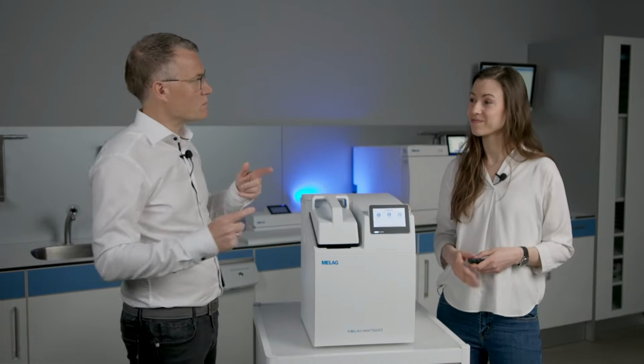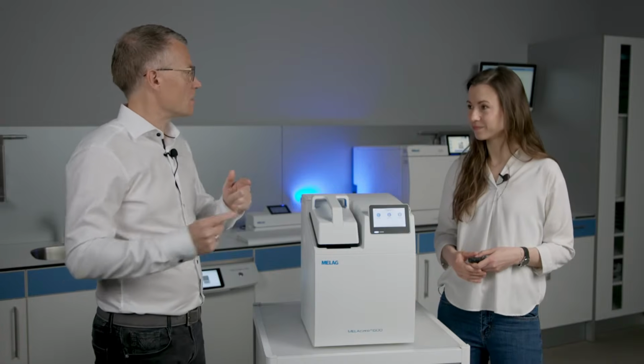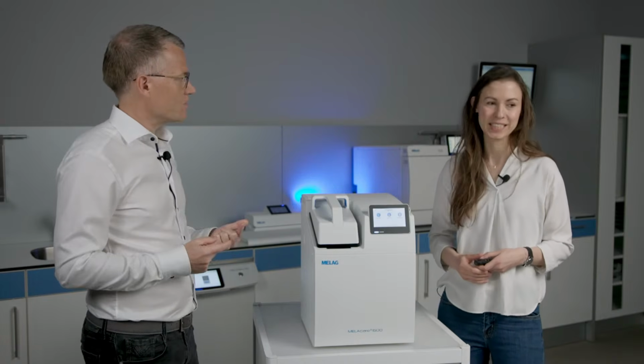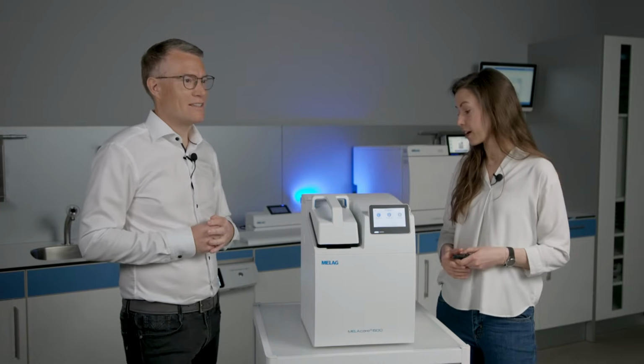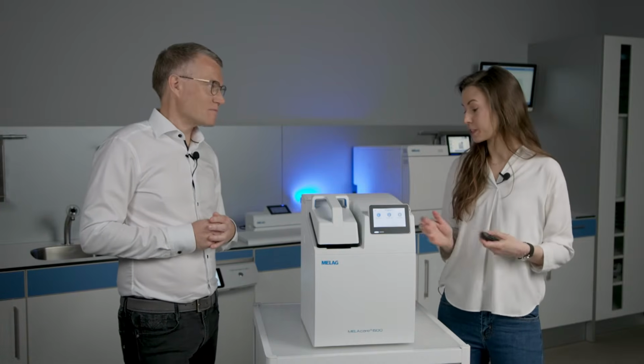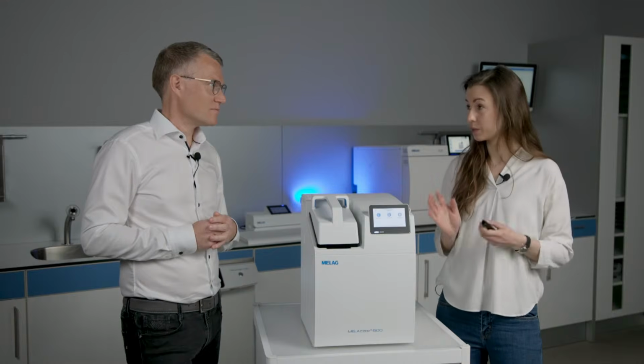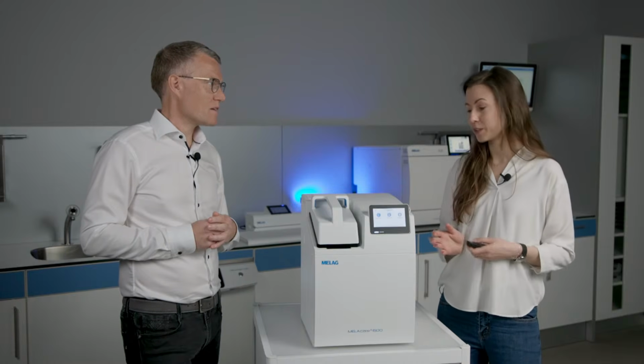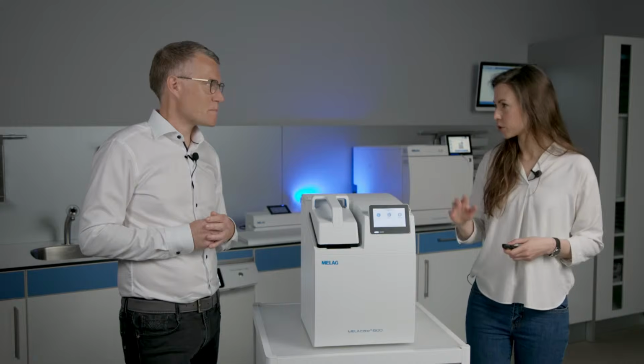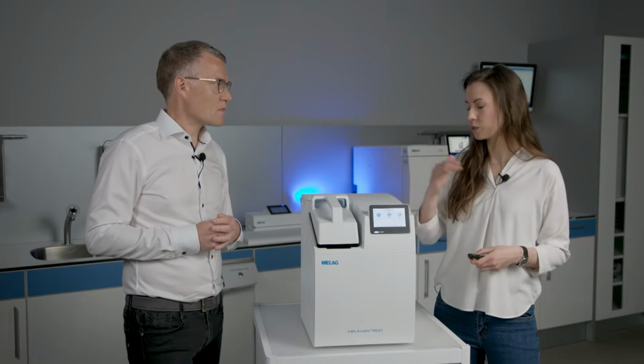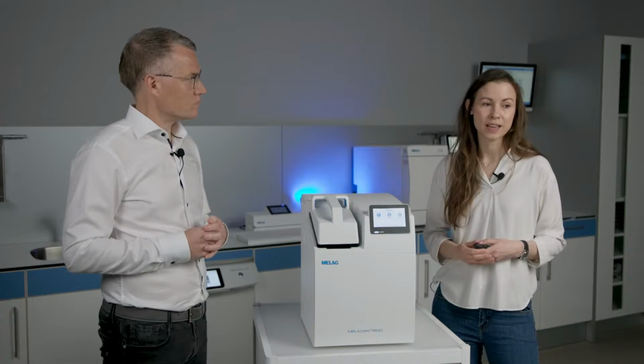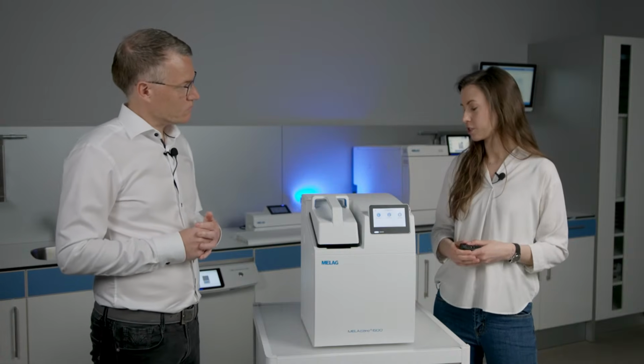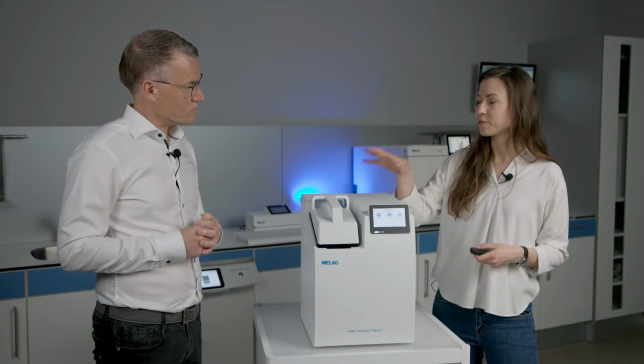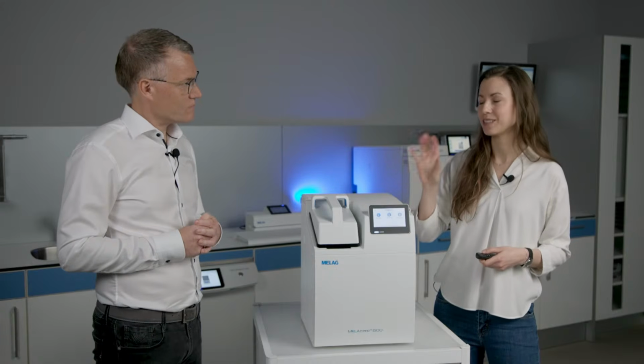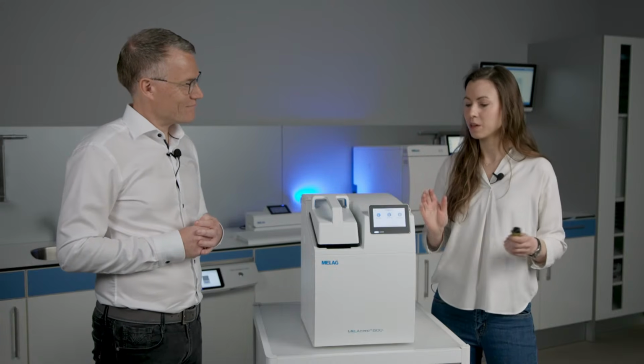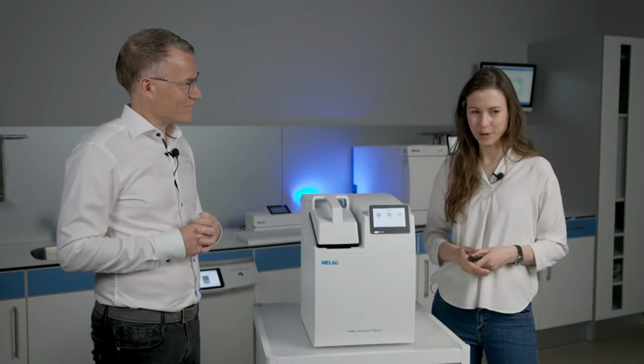We're always talking about inner and outer cleaning, inner and outer disinfection, and lubrication. That means you have safe reprocessing of the instruments after every patient. You also have a lower investment in additional instrument sets, since you can use them at a higher frequency. And lastly, you have a high level of protection for the life of the instruments, as they're well cleaned and well maintained to run smoothly for as long as possible.